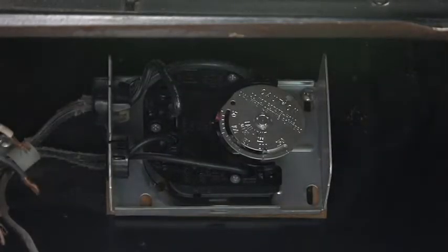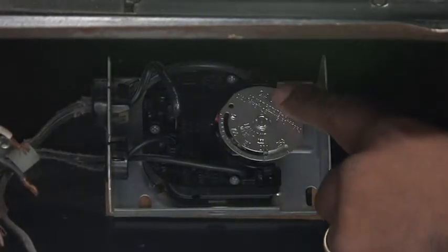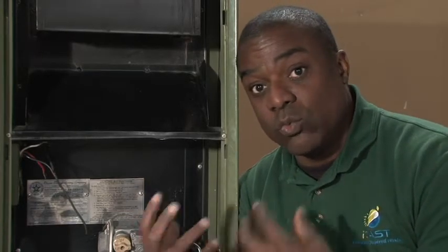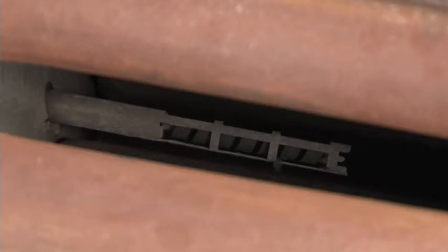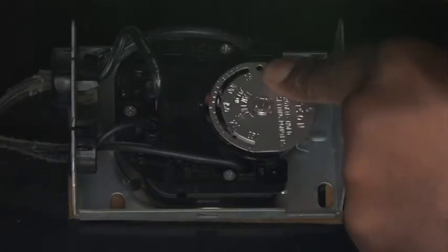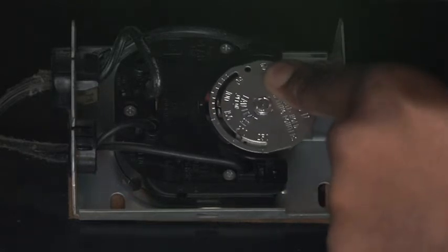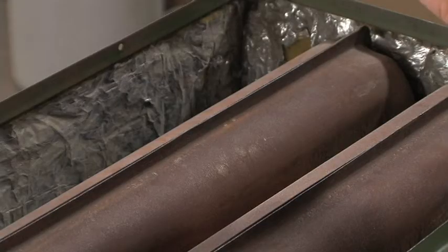Down below the draft diverter, we have this silver dial. That dial is called the fan limit switch. What happens is when the furnace gets a call for heat, it turns on the burners. Those burners then begin to warm the heat exchangers. That little probe in between the heat exchangers is connected to that silver dial. So as the heat exchangers begin to heat up, that silver dial begins to turn. Once that dial turns far enough, it hits the fan switch. And so the fan switch then turns the blower on, blowing air across the heat exchangers, extracting heat out of the combustion gases.